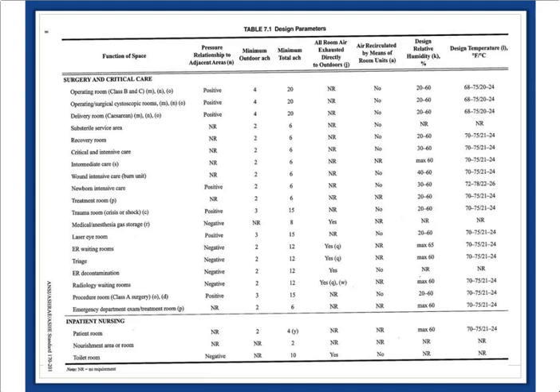In other words, we don't want to reuse any of that air. Are we allowed to recirculate air within a space? What are the humidity range requirements, low to high? Again, these aren't specifically saying what an operating room's relative humidity should be, but what the ventilation system serving an operating room should have the capacity to manage - the range it should be able to maintain for humidity levels, and the same for temperature. So for all types of different spaces within healthcare, this design document provides what those baselines should be.